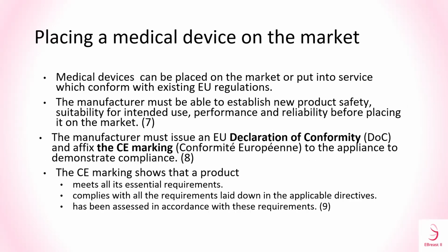Placing a medical device on the market. Medical devices can be placed on the market or put into service which conform with existing EU regulations. The manufacturer must be able to establish product safety, suitability for intended use, performance, and reliability before placing it on the market.